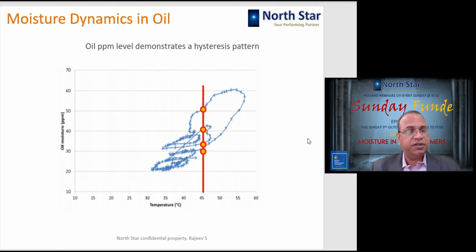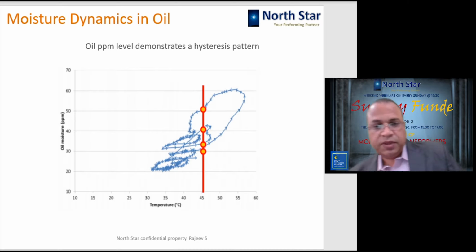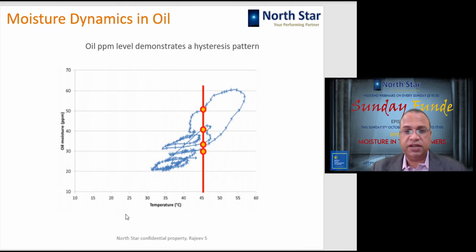Now again, looking at this moisture dynamics in oil, this is a graph plotted over a period of time on the basis of continuous monitoring, maybe around 6 months. If they have taken a reference of, say, 45 degrees centigrade, at different points of time they have got a different amount of ppm in the oil. What does that mean? The temperature is the same, but the ppm can vary depending upon the load condition of the transformer. So ppm is a very misleading parameter if not understood in the right context, and based on a wrong conclusion we can take wrong decisions. That is a very important aspect to understand about the moisture dynamics in the oil.